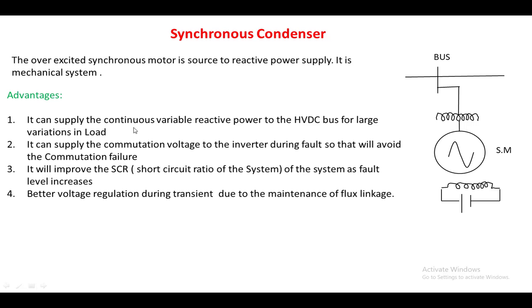The synchronous condenser has advantages and disadvantages. It can supply continuous variable reactive power to the HVDC bus during large load variations. It can also supply commutation voltage to the inverter, and if a fault occurs causing supply to drop to zero, commutation failure can be avoided. It improves the short circuit ratio during fault conditions.